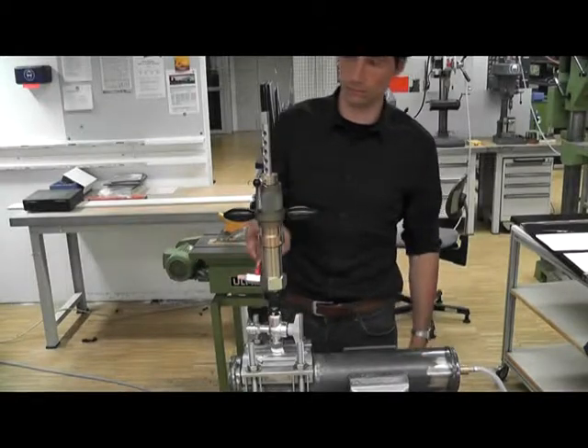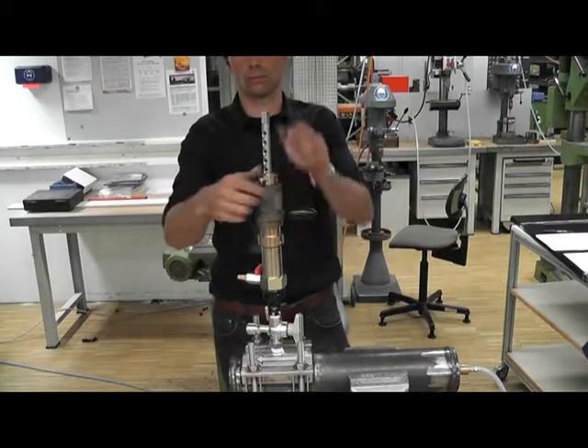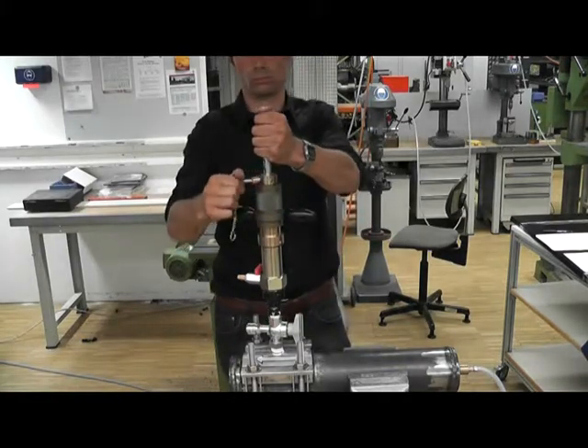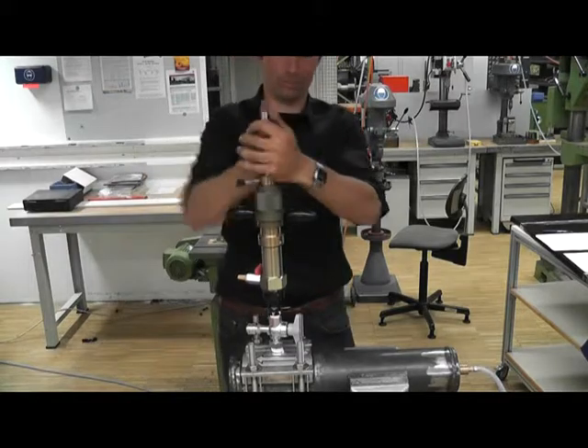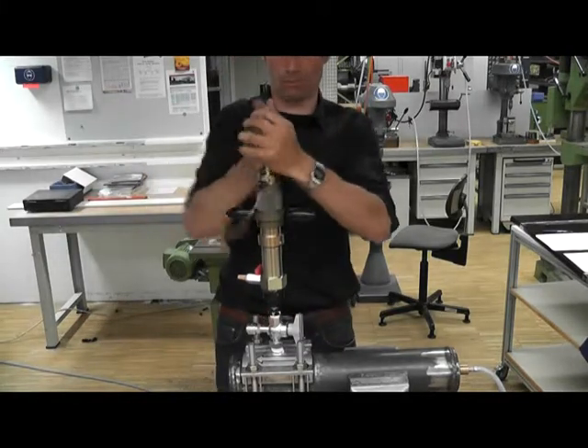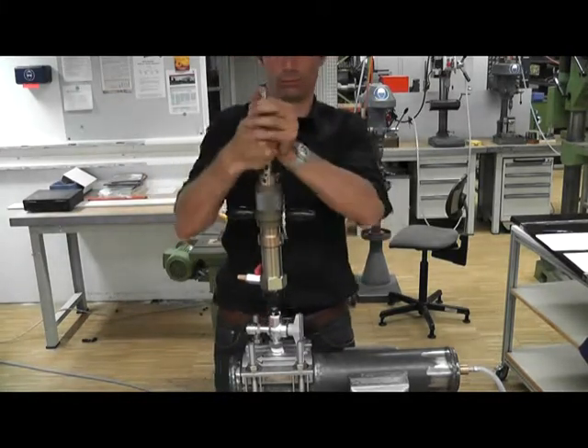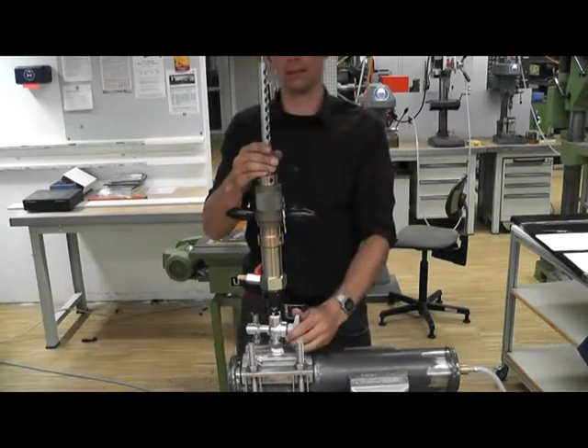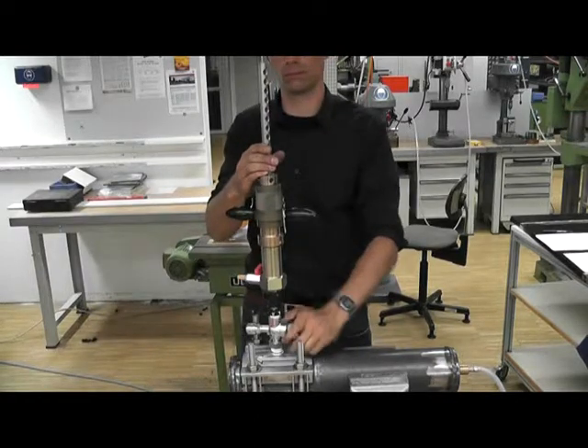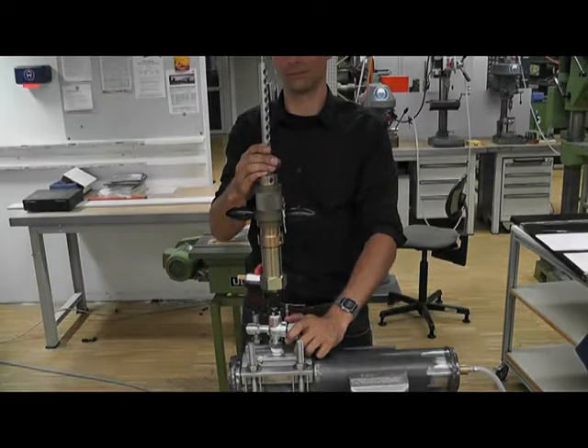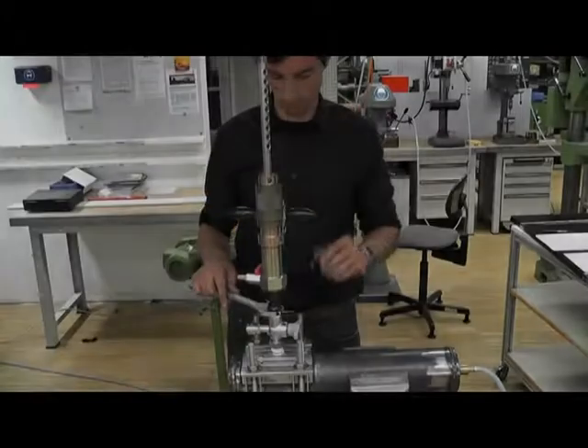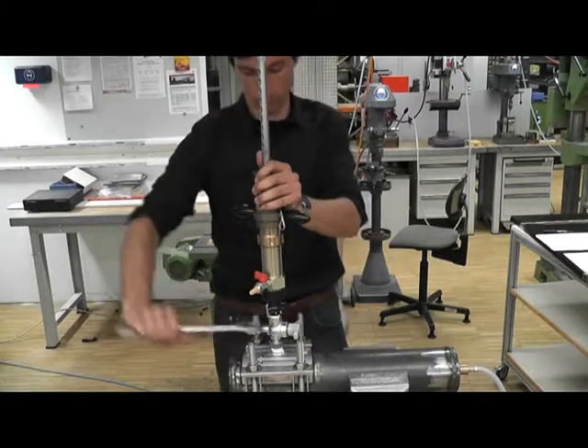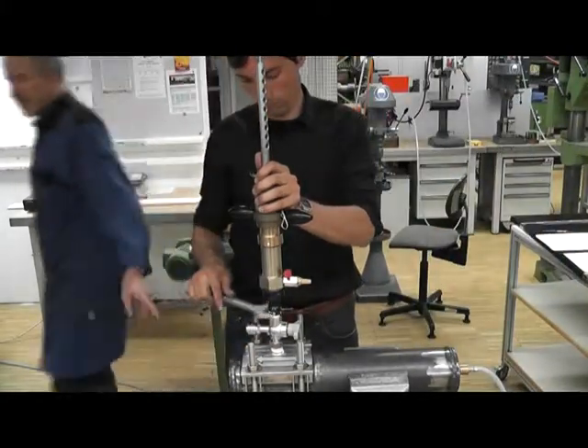Before you start to uninstall the driller, please prove that all screws are tightened. Now we have to uninstall the bolt. At this point, the driller can hit back till the back stop. Keep your body away from this area. If the driller isn't coming out by itself, try shaking and rotating to force the recoil of the driller. If the driller is at his end point, close the ball valve. If the ball valve is closed, you can remove the driller.